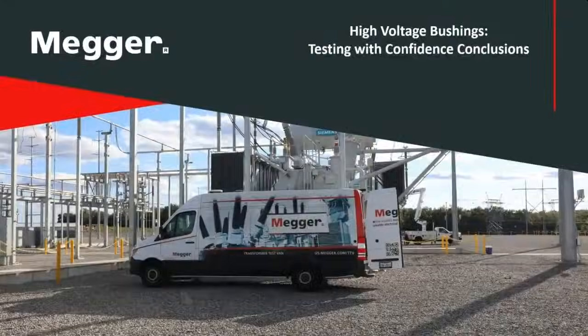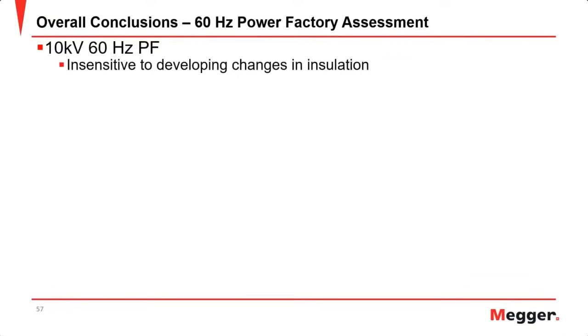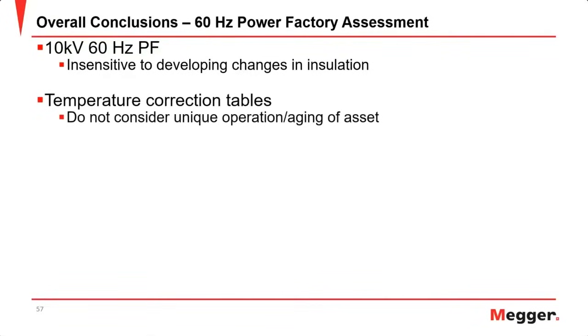So coming to some conclusions here, first of all, when we look at 60 hertz power factor, you are going to do the 10 kV 60 hertz power factor. I am not here to try and convince you to stop doing this. People have been doing it for decades and they will continue to do that. But what we do recommend is that you go a little bit beyond the 10 kV 60 hertz because it is very insensitive to developing changes in the insulation. And if you are using temperature correction tables, please keep in mind that these do not consider how that insulation has changed over time. They're really only meant for bushings or transformers that are in ideal condition, almost directly from the factory.